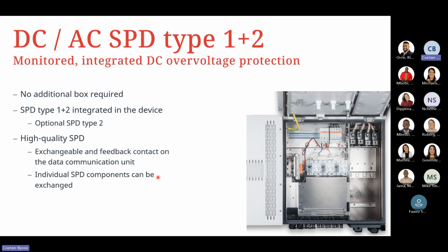What's also very handy on the Fronius Tauro is our integrated DC and AC overvoltage protection. So again, no additional boxes required. It's all installed internally on the DIN rail that's located inside the unit. It's a high quality SPD, so it's exchangeable, and there's the feedback contact on the data communication unit.